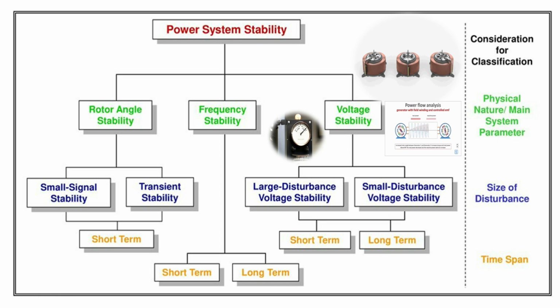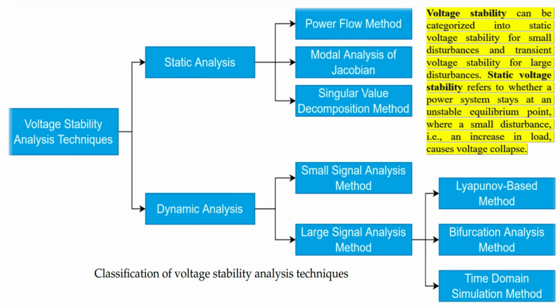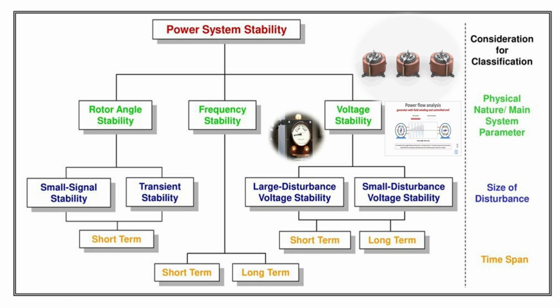The regional distribution of VRE is unbalanced, which requires a large amount of long-distance transmission, especially HVDC transmission. The general short-circuit ratio is derived to evaluate the static voltage stability of multi-infeed direct current, DC, systems under constant power and constant extinction angle policies for line commutated converters, LCCs. However, although generation and load characteristics contribute a lot to static voltage stability, the stability of power systems with power electronics greatly depends on the control strategies of power electronic devices and the power injected through the devices. Namely, increasing DC injections would jeopardize the voltage stability of an AC system.